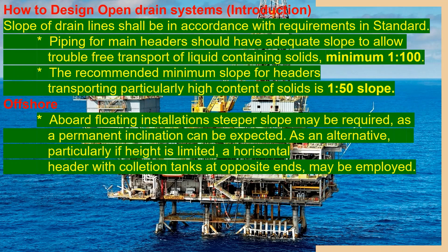The recommended minimum slope for headers transporting particularly high content of solids is 1 to 50. When offshore, on board floating installations, a steeper slope may be required as a permanent inclination can be expected. As an alternative, particularly where headroom is limited, a horizontal header with collection tanks at opposite ends may be employed.